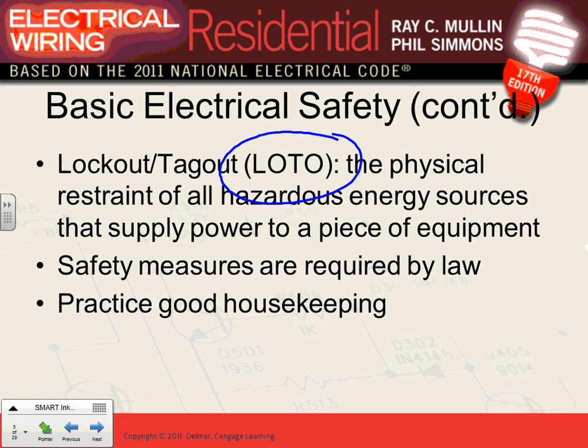You push the button to de-energize the air handling unit. Second, you put the disconnect in the off position. Third, you lock it with your lock, put a tag with your name on it, and keep your key with you at all times. Then you work, and you measure that there's no voltage after you lock it.